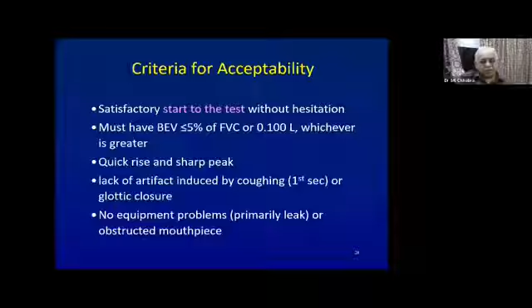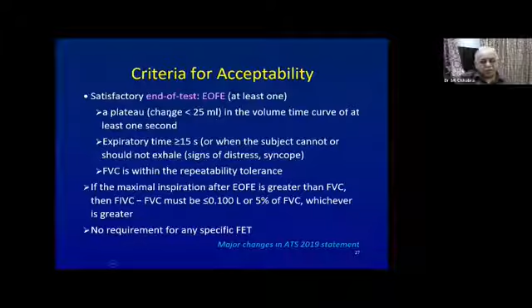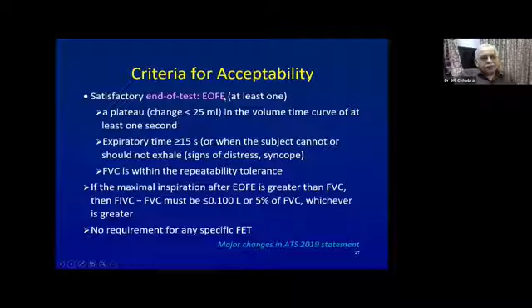There should be a quick rise and a sharp peak. There should not be any coughing or glottic closure, and there should not be any leak in the equipment or from the mouthpiece. So an experienced technician can make this out by looking at the tracing. Then the end of the test must be satisfactory. This is the end of the forced expiration. So either there is a plateau, that is a volume change of less than 25 ml in the volume time curve for the last 1 second, or an expiratory time of more than 15 seconds. Earlier there was a time limit of at least 6 seconds that has been removed in the ATS 2019 statement.